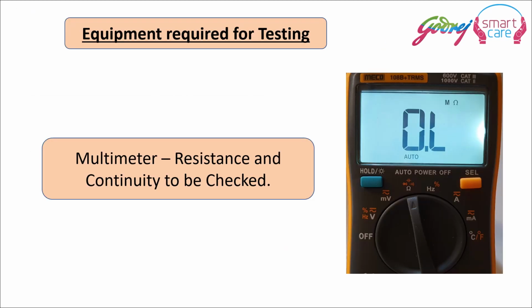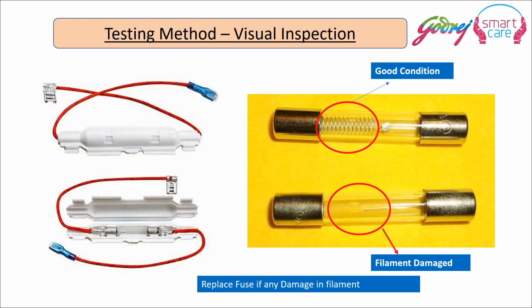The equipment required for testing is a multimeter. Check the resistance, or we can check the continuity. Both of these will give equivalent results. We can also visually check through the glass tube whether the fuse is broken or whether the fuse is attached.